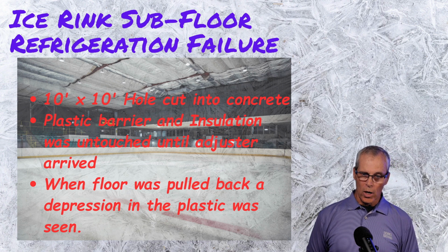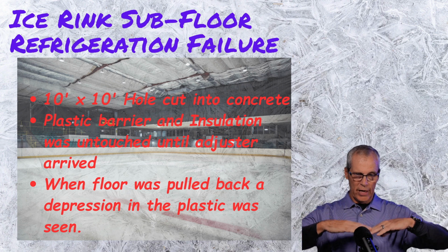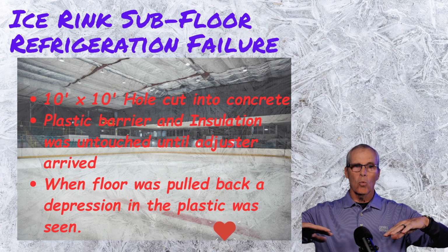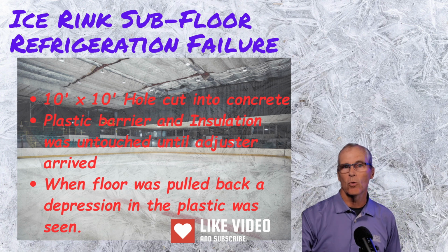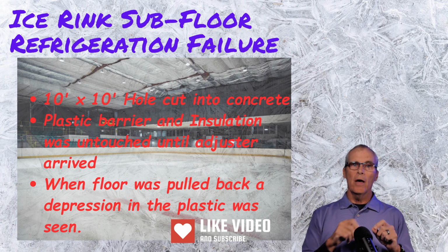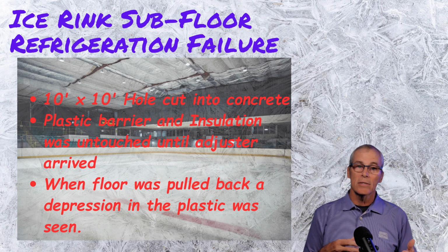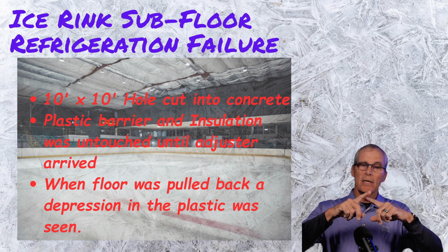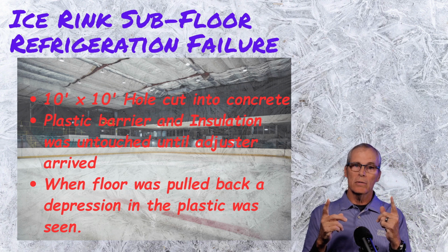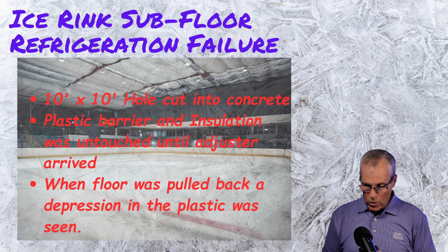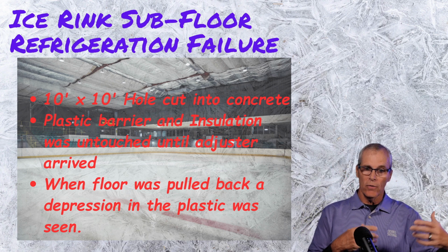Okay, so the concrete's gone. We're looking at the floor. There's plastic over that sand, and the sand is kind of washed away in one certain area. Well, everybody points to that and says that's where the leak is. So we carefully go down there and we cut open the plastic, and we look and we find in the sand a plastic T fitting, part of that heating system, and it's broken and snapped off. So we get a saw, we cut the other two legs of that T off, and we start to look at it very carefully.